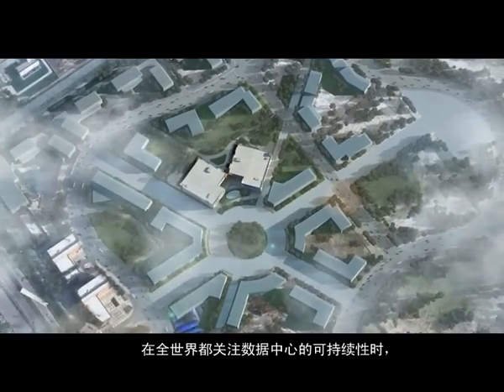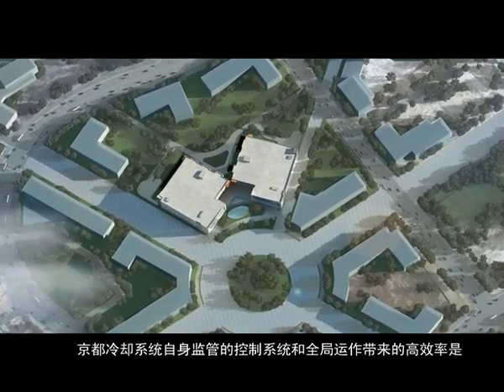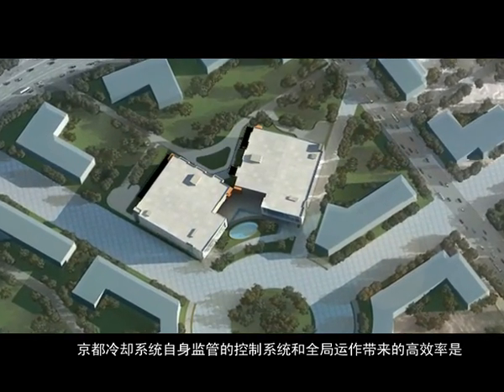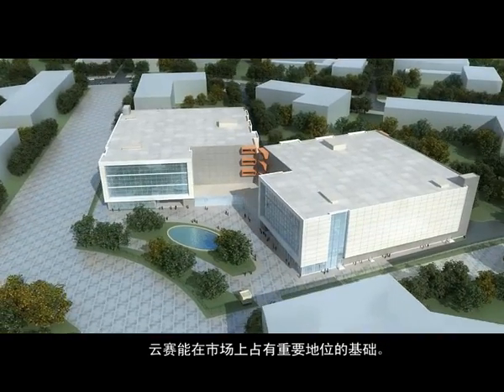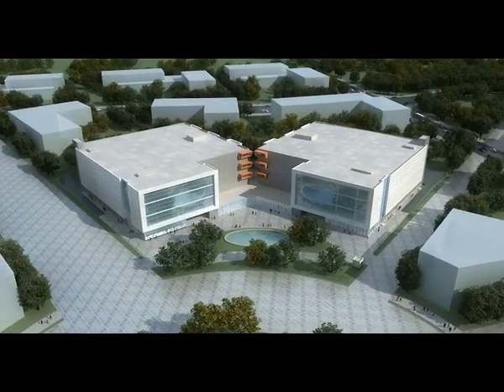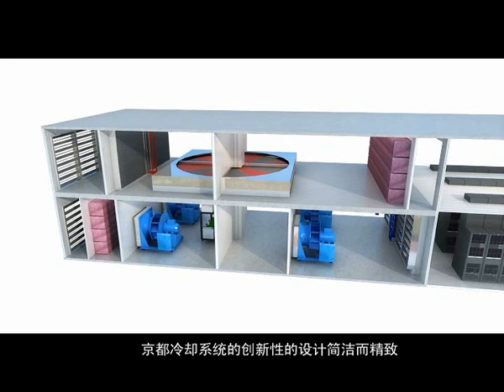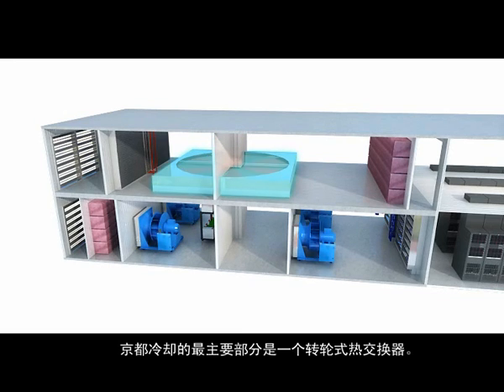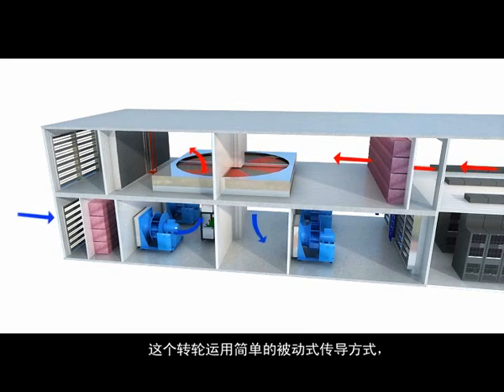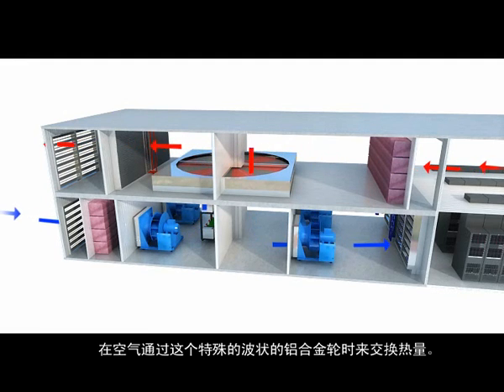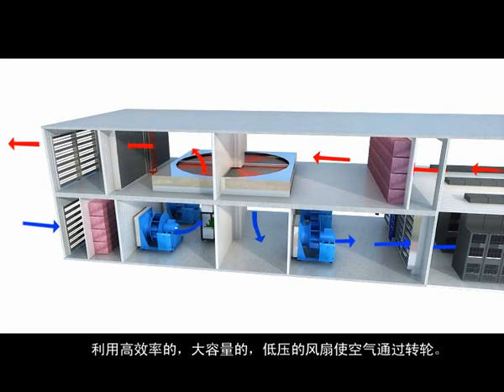With the universal focus on sustainability in data centers, KyotoCooling's self-regulated control system and overall operating efficiency are the foundation of Cloudsite's value proposition in the market. While KyotoCooling's innovative design is simple and elegant, it is the most advanced system currently available for data center cooling. The primary component of KyotoCooling is a rotating heat transfer wheel. This wheel uses simple passive conduction to transfer heat as air passes through the special corrugated aluminum of the wheel. Very efficient, high-volume, low-pressure fans are utilized to move air through the wheel.